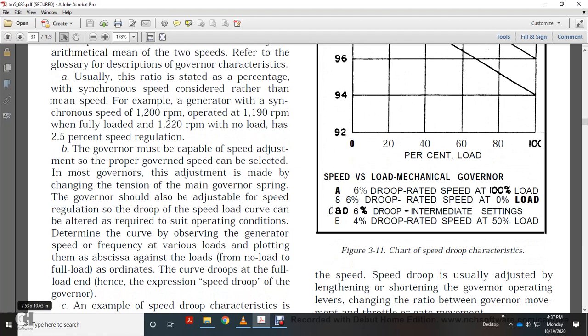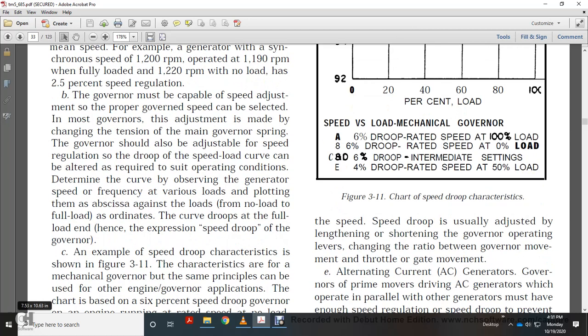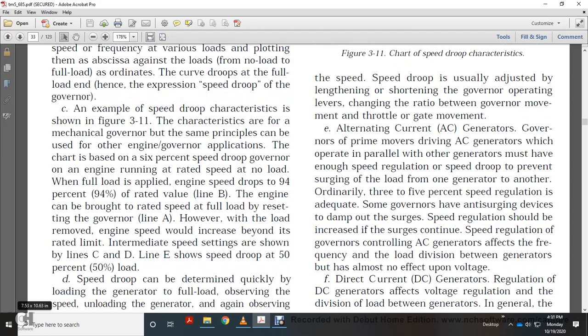The governor must be capable of adjusting to the proper speed. Governor speed adjustment is made by changing the tension of the main governor spring. The governor should also be adjusted for speed regulation with a droop. The speed-load curve can be altered as required for suitable operating conditions — observed by plotting generator speed and frequency at various loads from no load to full load.